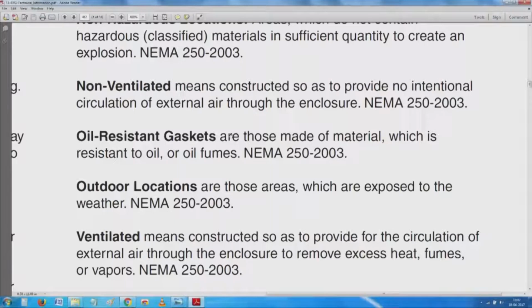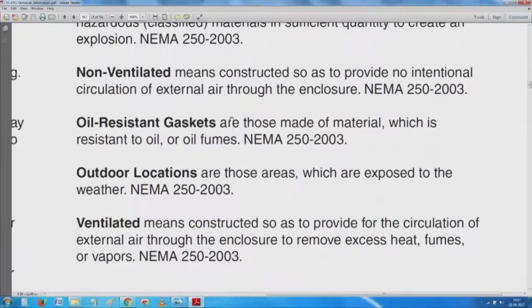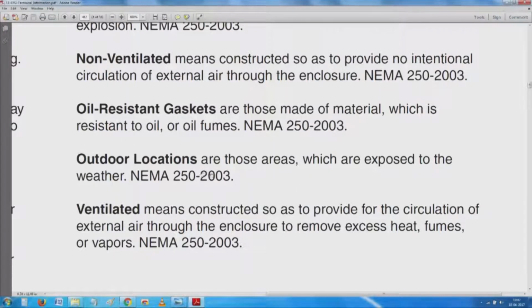If you go down, we have non-ventilated cabinets - no intentional circulation of external air through the enclosure, only it may get in through the gaps. Ventilated means constructed so as to provide for circulation of external air through the enclosure to remove excess heat, fumes or vapors.